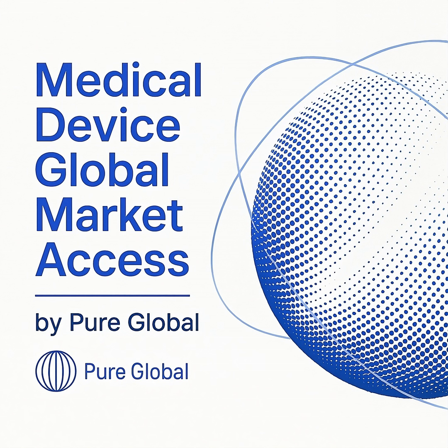This document specifies the performance benchmarks, safety standards, and testing methods for your device, and it forms the basis for local testing. Even with extensive testing data from your EU submission, China requires in-country type testing at an NMPA-accredited laboratory. These tests validate the device against the standards defined in your PTR. While provisions introduced in 2021 allow for self-testing reports in some cases, this requires the manufacturer to have the necessary qualified testing capabilities. Another significant hurdle is the Clinical Evaluation Report, or CER.